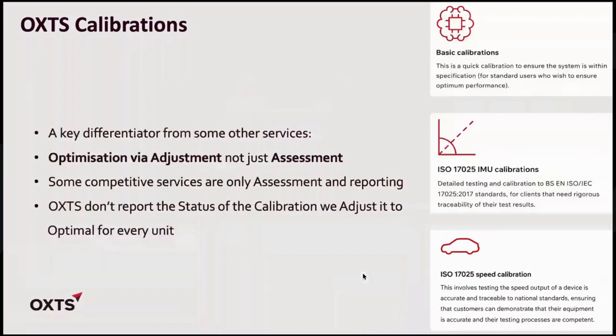And another question that comes up quite a bit, that I thought I would cover at the end of this webinar, is the difference in an OXTS calibration compared to what some other services or other groups offer. Very importantly, one of our differentiators that's not always fully understood because of the terminology is when some companies or services talk about calibration, all they mean is measurement of where your device is compared to where it originally was, or the measurement of where your device was compared to an ISO standard. Here at OXTS, one of the things that differentiates our basic calibration and our ISO calibration is we don't only measure where you fall inside the standard lines. We always adjust you back to an optimum setting.